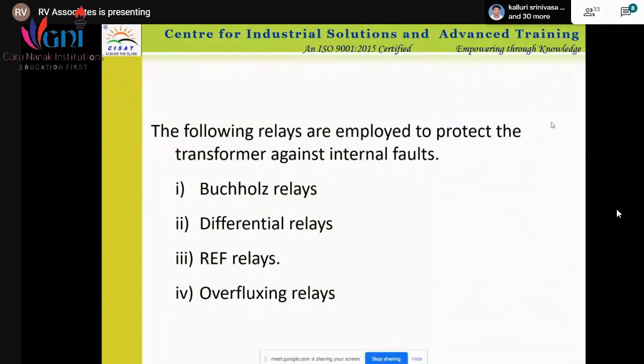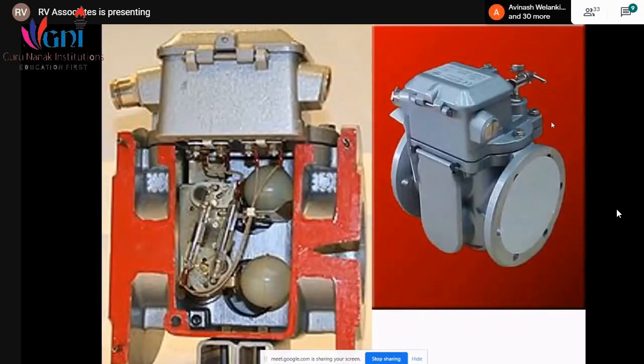Then various other relays are there, like the Buchholz relay, differential relay, REF relay, and overfluxing relay. At present, we are using numerical relays. Except for the Buchholz relay, all other relays are covered in numerical relays. This Buchholz relay is a gift to the transformer. Why is it a gift? Because it will give you a clear indication of the condition of the transformer, and it will protect the transformer from all internal faults. Alone, this one device can do 99% of the protection. This is the Buchholz relay.